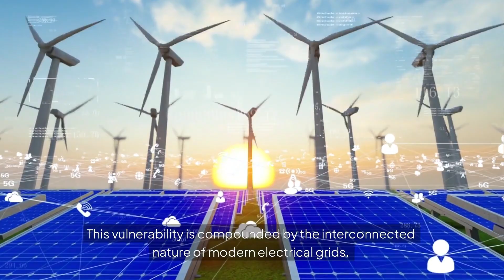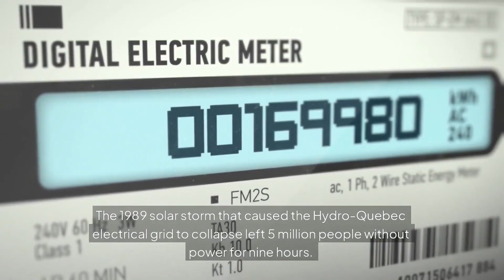This vulnerability is compounded by the interconnected nature of modern electrical grids. A disruption in one part of the system can trigger cascading failures, chain reactions that spread through the network like falling dominoes. The 1989 solar storm that caused the Hydro-Quebec electrical grid to collapse left 5 million people without power for 9 hours. This wasn't a Carrington-level event; it was approximately 1/10 the strength.